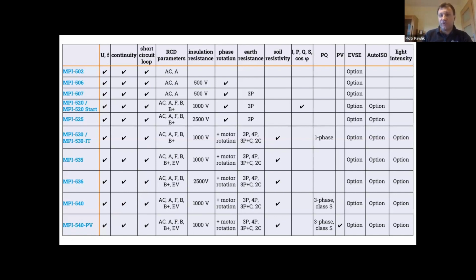Further on, in case we would like to measure electrical installations in buildings, we can check, for example, the MPI 506, which can also check insulation resistance and phase rotation, and meters like the 507 or 520. These models can also check earth resistance. And further on, each model has some extension. Right now, our higher models allow us to check all parameters of electrical installations as described by the IS 732. Also, in the case of car charging stations, because we can check the EV type of the breakers. It has a built-in three-phase power quality analyzer of type S. And it can also check the safety of photovoltaic networks. So PV here stands for photovoltaic.